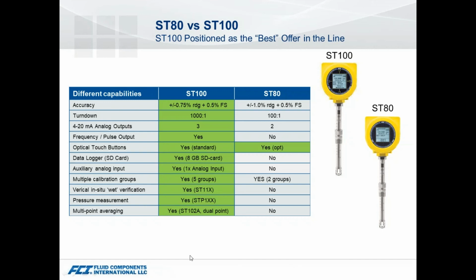The pressure option, and then the one we'll talk about here a little bit later, a multi-point averaging system where you'd have 2 flow elements averaged into one set of electronics, for making higher accurate measurements in larger lines, or sometimes straight run conditions prevent you from getting there.